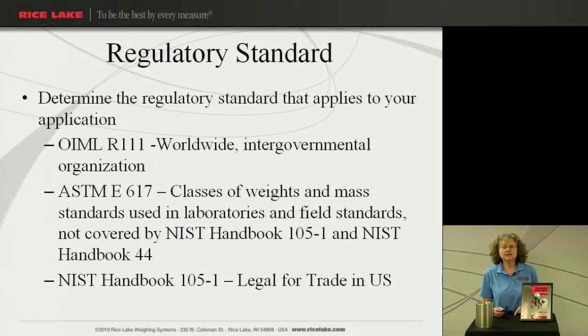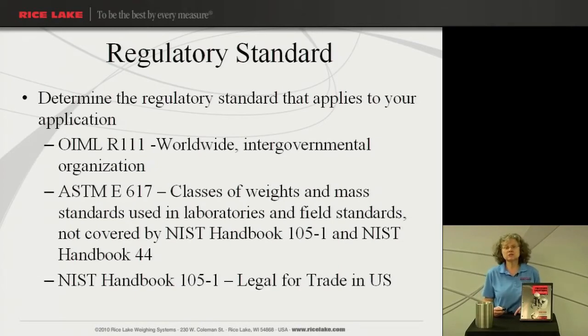ASTM E617 covers classes of weights and mass standards used in laboratories and field standards not governed by NIST Handbook 105-1 and NIST Handbook 44. This is primarily used for the higher accuracy class weights here in the United States. If there is a requirement internationally and you're also going to be doing business in the United States, you might want to look at these guidelines as well to make sure you've considered all requirements. NIST Handbook 105-1 is used for legal-for-trade in the United States.